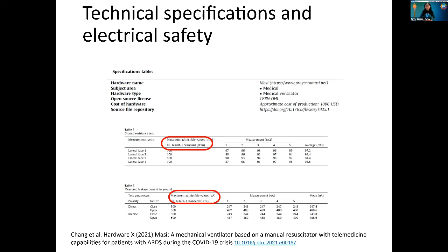Also, in this HardwareX article, we describe all the technical specifications that we needed to accomplish in order to test the different prototypes, such as, for example, electrical safety. Besides electrical safety, we were also able to show that the technical characteristics and performance assessment were positive. That means that when we measured parameters regarding the three ventilation modes that we were proposing, the ventilator performed within the expected ranges and what would be part of the standards for this type of instruments.